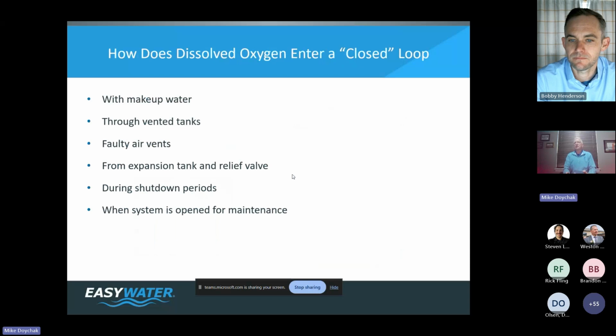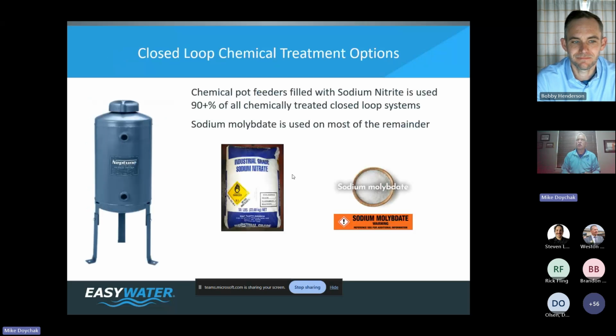So let's look at this. We're dealing with a closed loop. If we're dealing with a closed loop, how does dissolved oxygen get in there? Well, through all of these ways here. We've got makeup water, we've got vented tanks, you've got leaks, you've got shutdown periods for maintenance, whatever that would be. Each time you are at risk of adding more dissolved oxygen in and ultimately adding more corrosion.